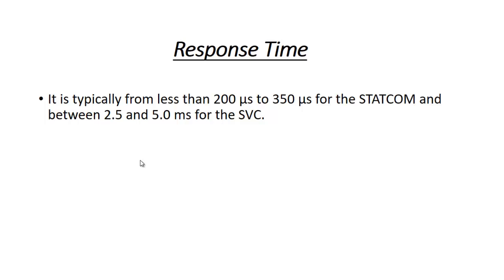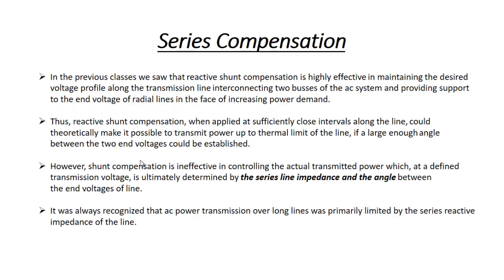The response time for the STATCOM is less than 200 to 350 microseconds, while for the SVC it is 2.5 to 5 milliseconds. So the STATCOM is also faster than the SVC. Overall, both STATCOM and SVC are used for shunt compensation — reactive power control or voltage control. Now we will move to series compensation.